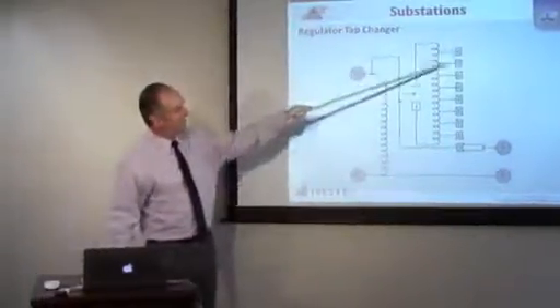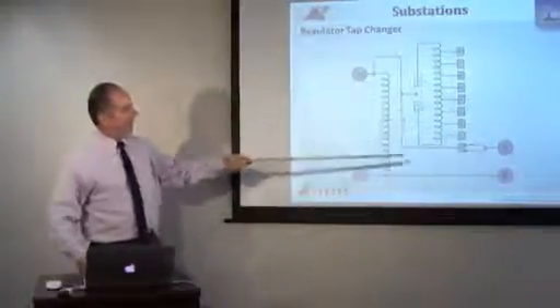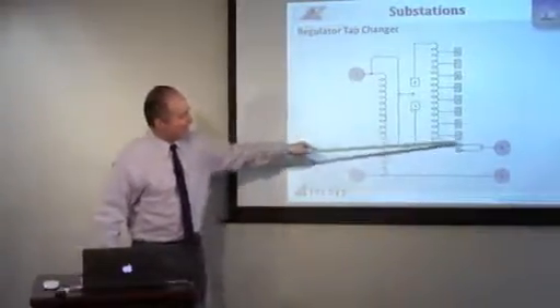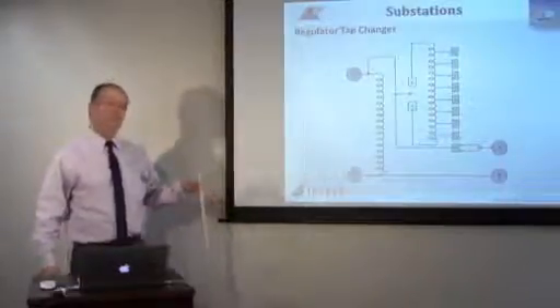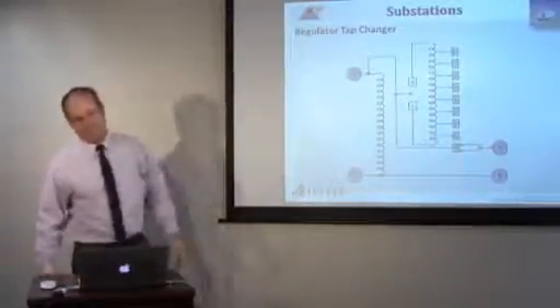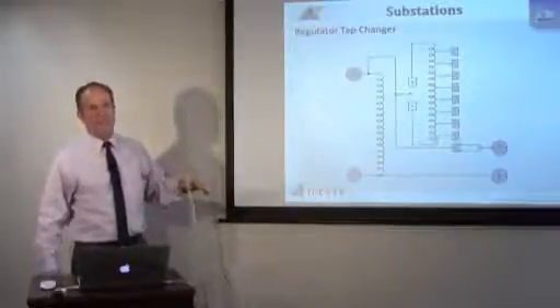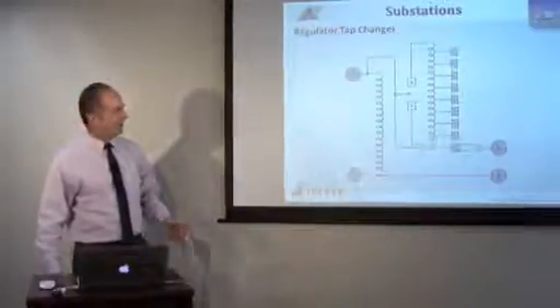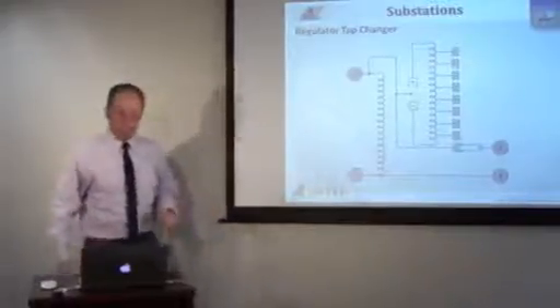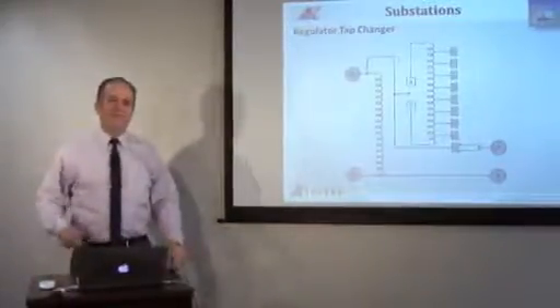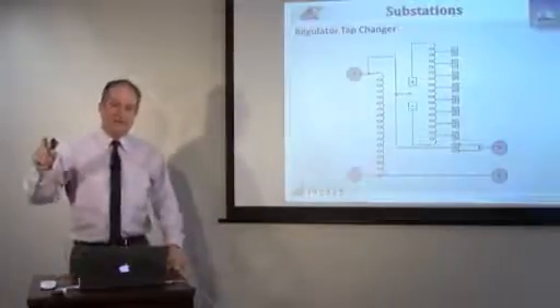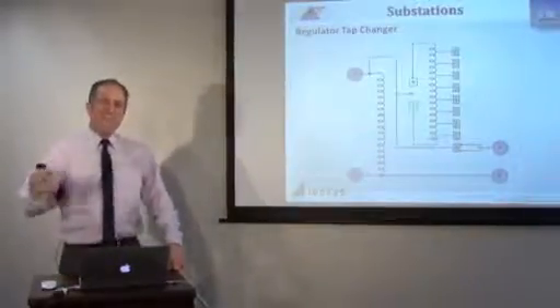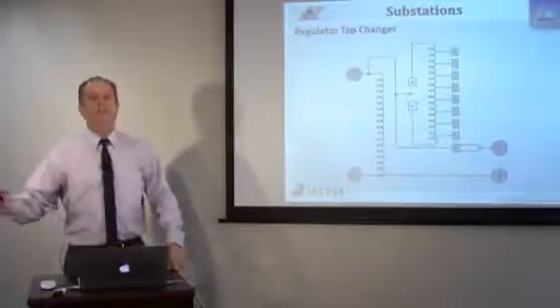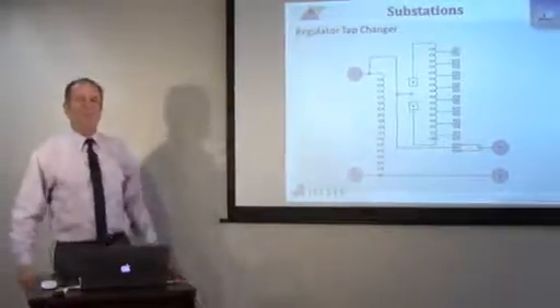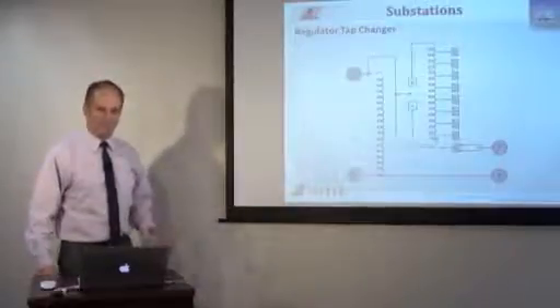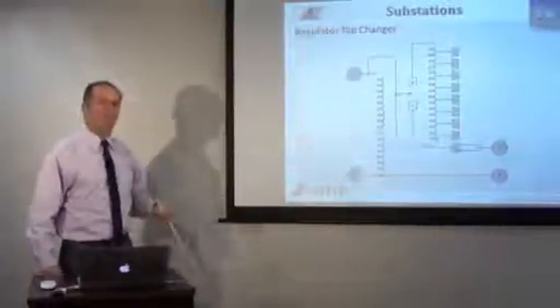Normally, you have 8 steps, okay, and each one has a half position, so you basically get 16 positions raising, 16 positions lowering, plus neutral is 33 positions to go plus or minus 10%. And that boils down to about 45 volts per tap change on the primary, which results in about 0.8 volts per tap change on the secondary. Like the 120 would go to 120.8 if the regulator changed a tap.